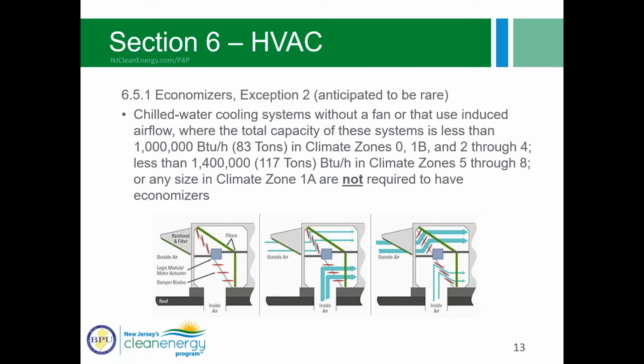All right, so again, with economizers, this one is in section 6.5, so it's a prescriptive one. This is a caveat: if there is a chilled water cooling system that does not have a fan or has induced airflow and is under specific capacities, the economizer would not be required. So this is something to keep in mind for when your projects are not the typical or standard design, as ASHRAE 90.1 does have different provisions for those system types as well.